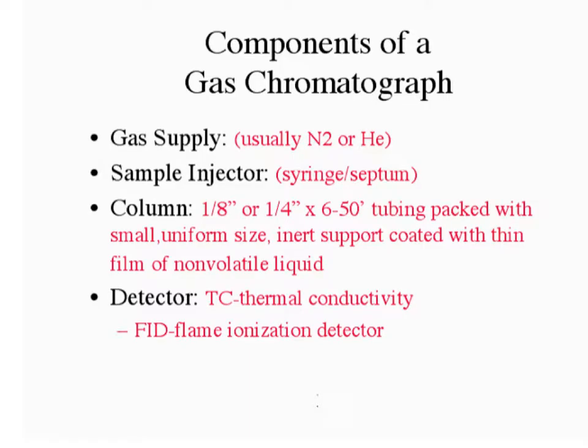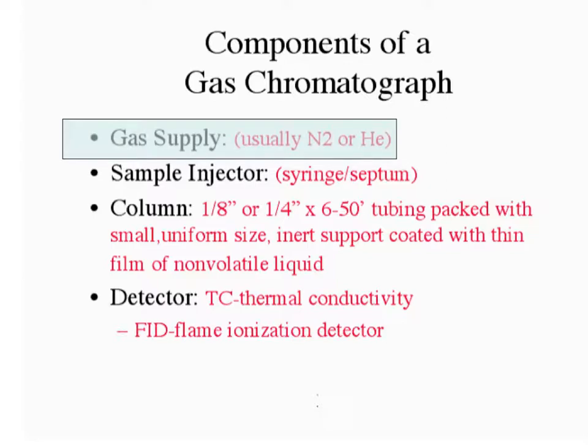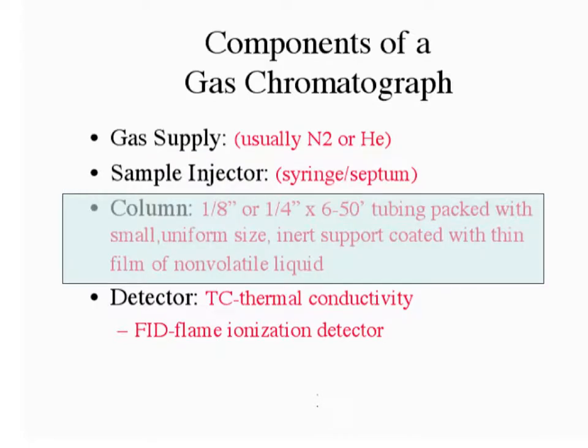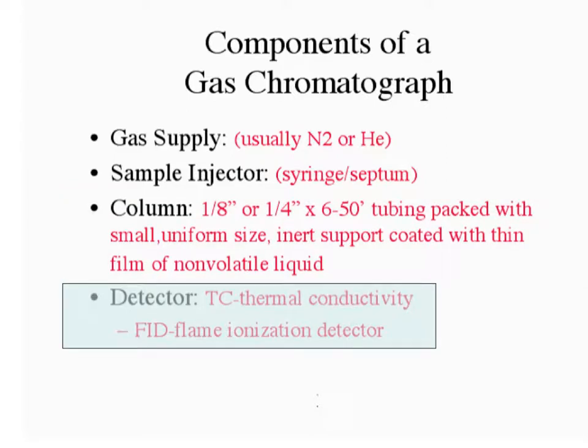All gas chromatographs contain the same four basic parts. First, you need a gas to push the sample through the column. Inert gases are used because they will not react with the sample. Second, you need a place and a way to introduce your sample into the instrument. Third, you need a column where partitioning can take place between the gas and liquid phases. Last, you need a way to detect your components once they have been separated and leave the column.